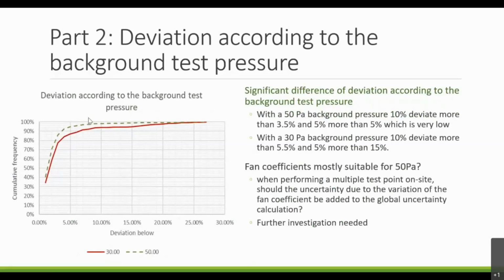Interesting results come with the background test pressure. When a building airtightness test is performed, the pressure between inside and outside the building varies usually between 10 and, let's say, 50 or 70 Pascal. And so when a calibration laboratory is performing a calibration, they also impose a pressure difference between inside the calibration chamber and outside, on both sides of the measuring device. Usually they use 50 Pascal as a background pressure, but there is no requirement on that, so some of them use 30 Pascal instead of 50 Pascal as a background pressure.